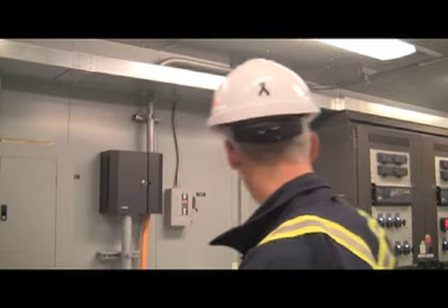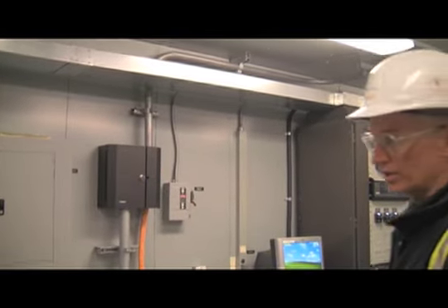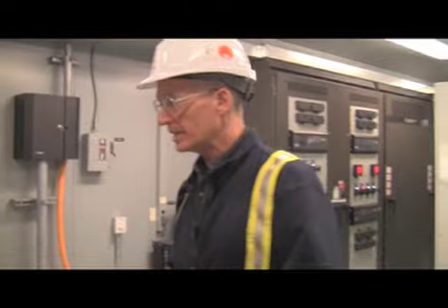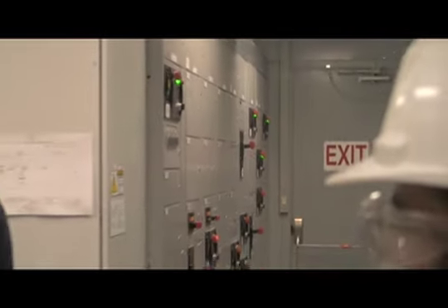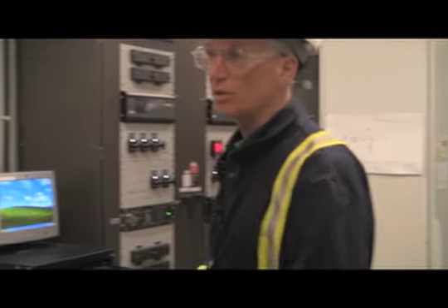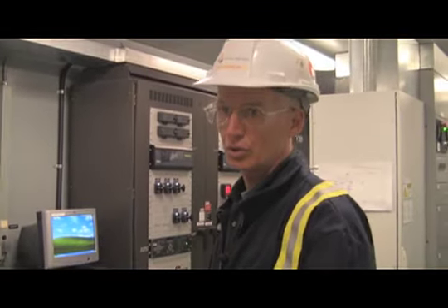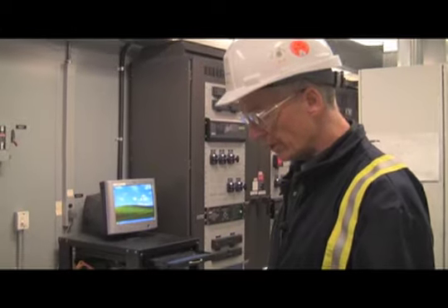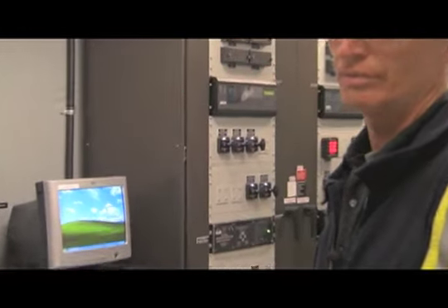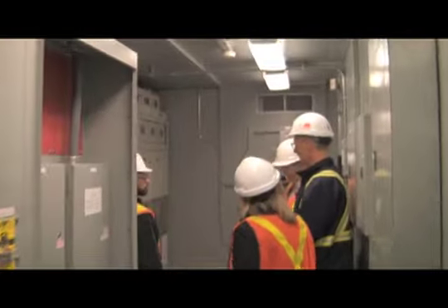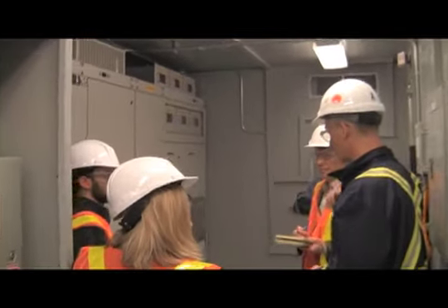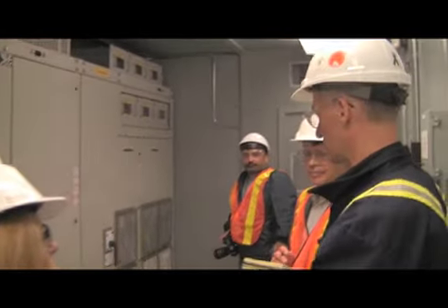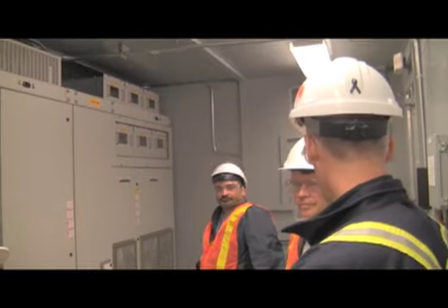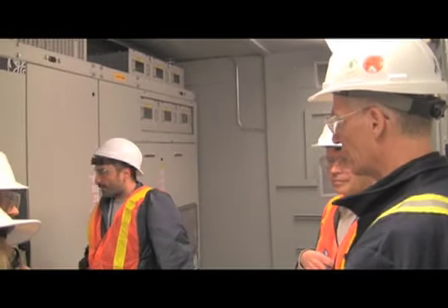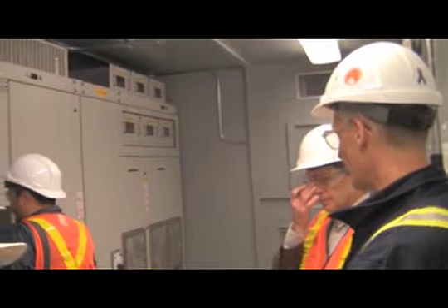And the way these little control packs are structured is basically to facilitate maintenance. It's like a little mini control room right here too. They can fully operate the unit from here in addition to the control room. There's only one area for the steam turbine, and that's in the control room. So basically what happens in here, the other module we're in is for control. It's monitoring the operation, it monitors the startup and whatnot. The equipment in here actually performs the work.